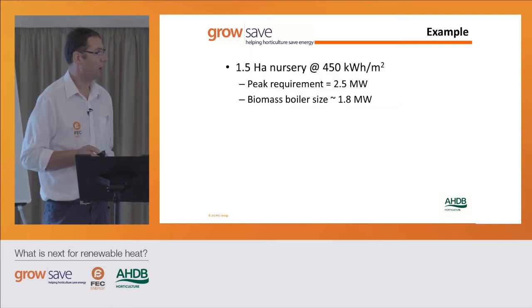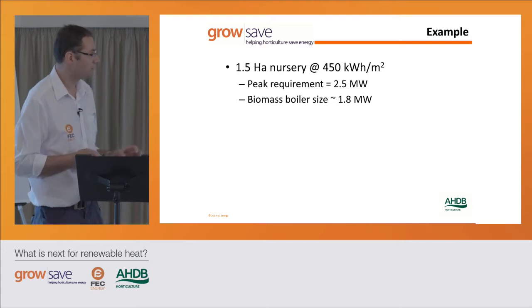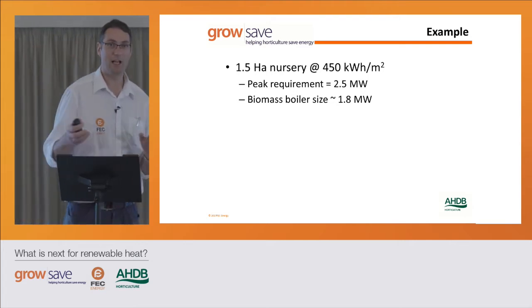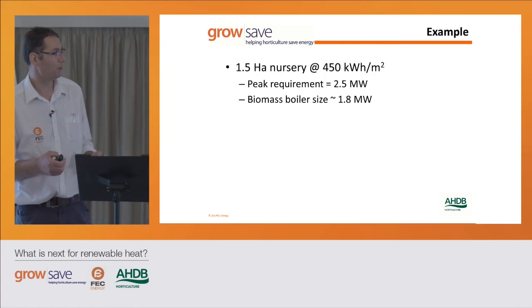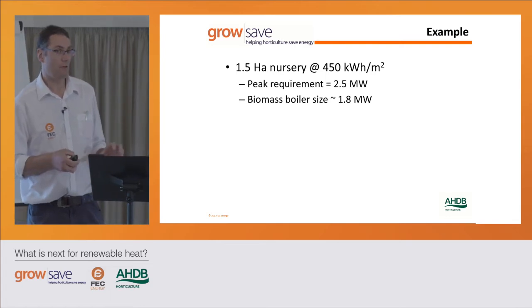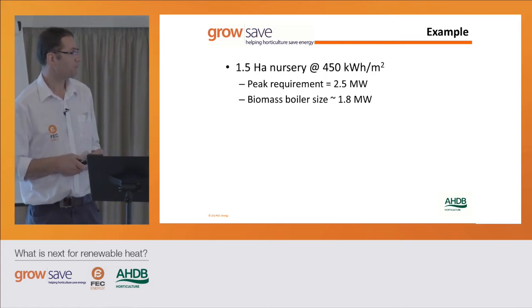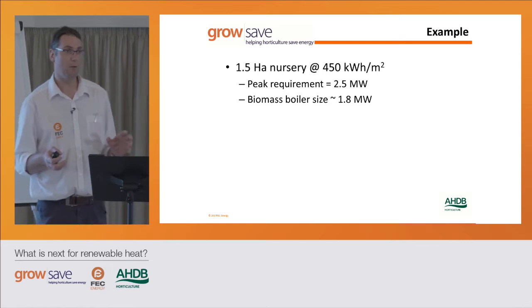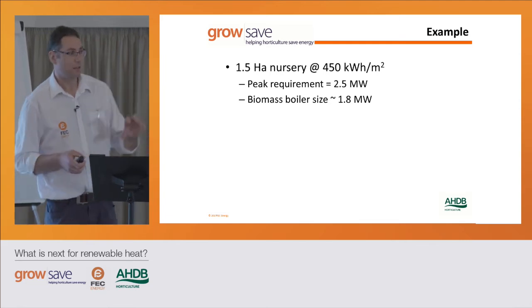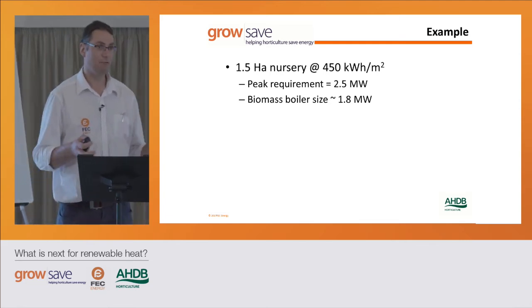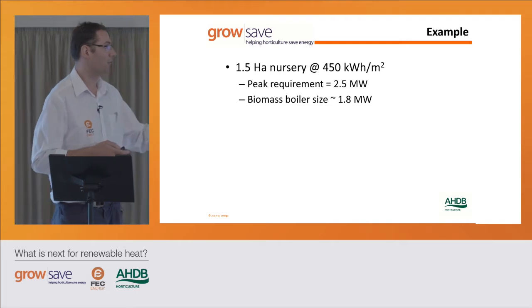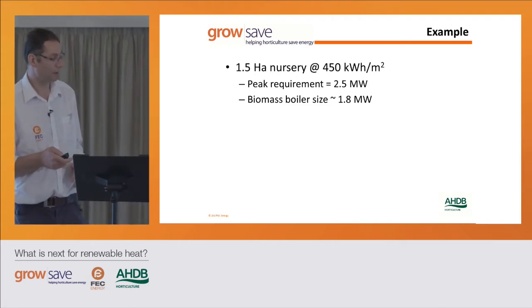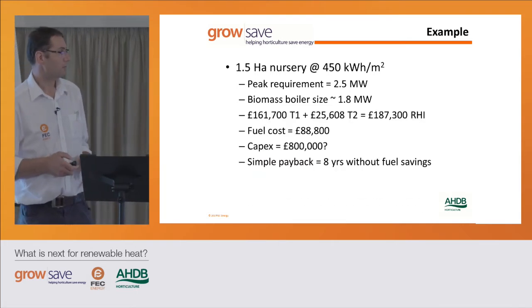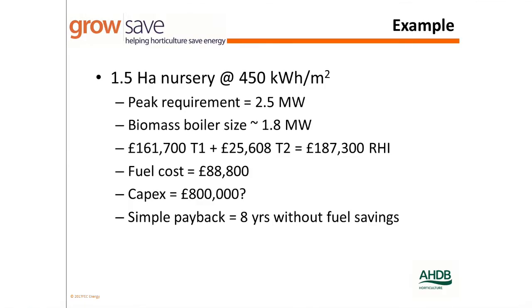Just a quick example: a typical 1.5 hectare nursery, 450 kilowatt hours per square metre, if you can call that typical - that's around a protected edibles level. Peak requirement 2.5 megawatts. Using a rule of thumb of 6 to 8 watts per square metre per degree C, you might end up with a biomass boiler around 1.8 megawatts in size. Someone can correct me on the capital cost later if I've got that wrong, but it's around that order.